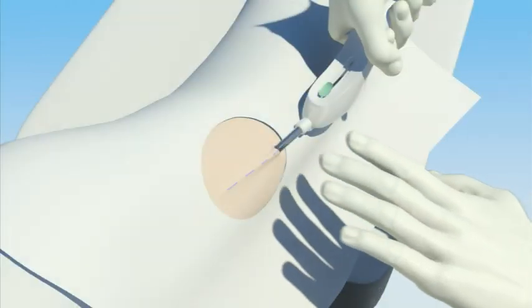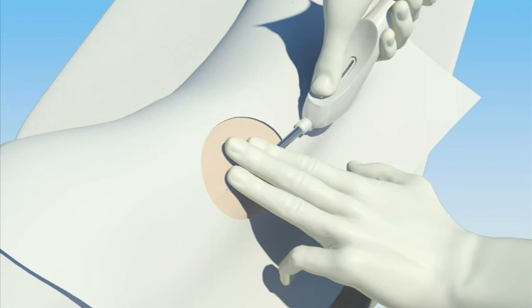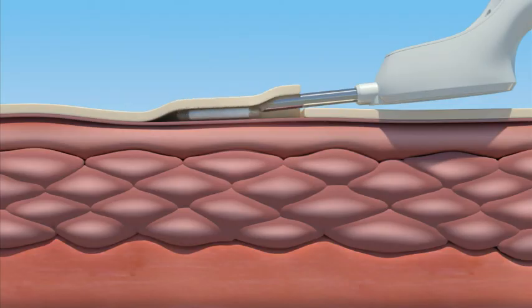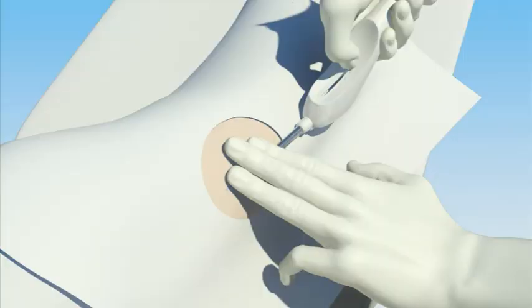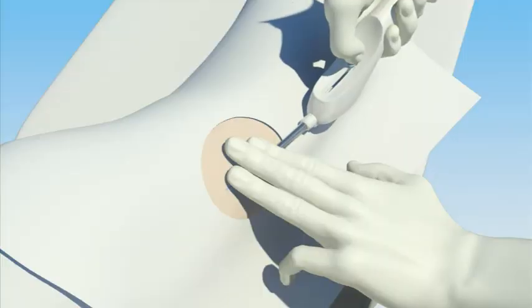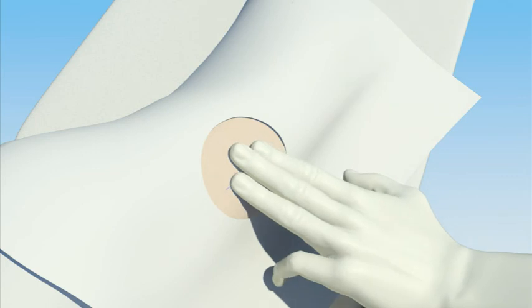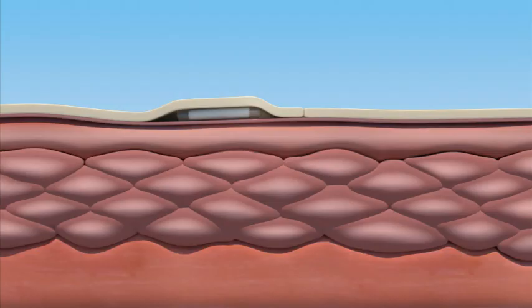While holding the insertion tool firmly in place with the base against the patient's arm, press the green retraction button to release the locking mechanism. Then slide the button back towards the handle while keeping the body of the device in place. Do not further advance the cannula once the retraction process has started. Retraction causes the cannula to withdraw from the incision, leaving the implant in the subcutaneous tissue. Apply pressure to the skin over the implant whilst withdrawing the device from the incision to ensure that the implant remains in the subcutaneous position.